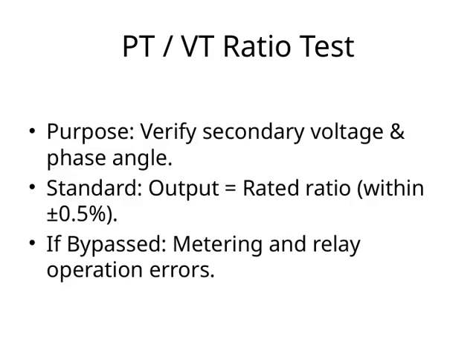Now, if this test is bypassed or not performed properly, it can lead to metering errors and relay operation issues. These errors could result in incorrect system readings or even improper relay actions, which might compromise the safety and stability of the system. So, in essence, the PT/VT ratio test is a vital step to ensure that all measurements and protective functions are working as intended, maintaining system integrity and safety.